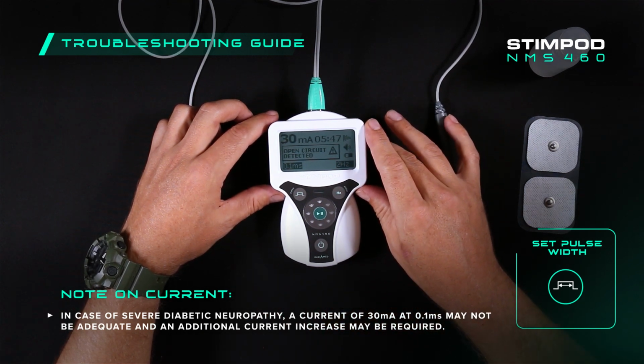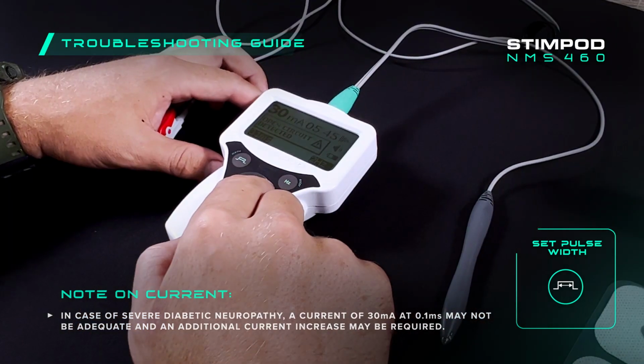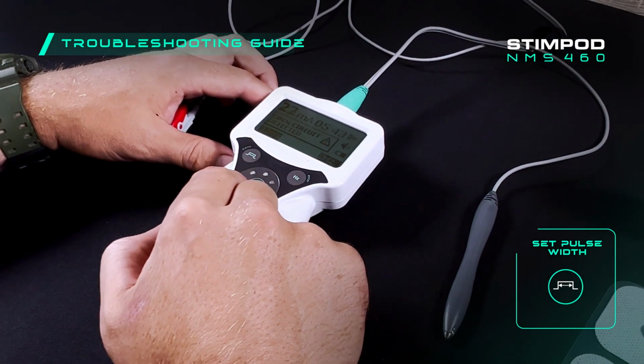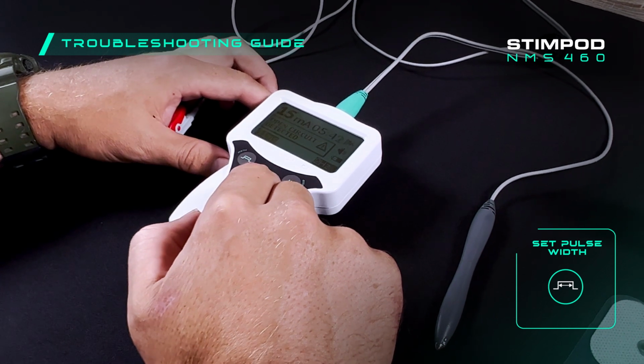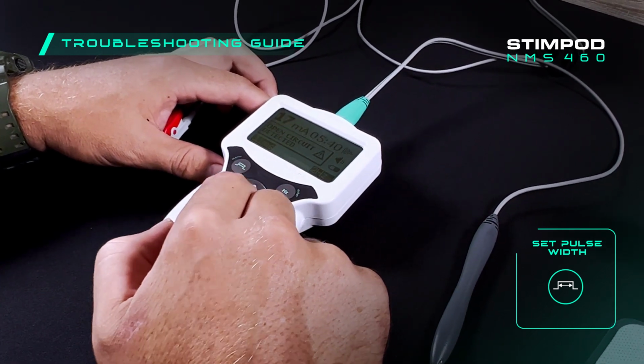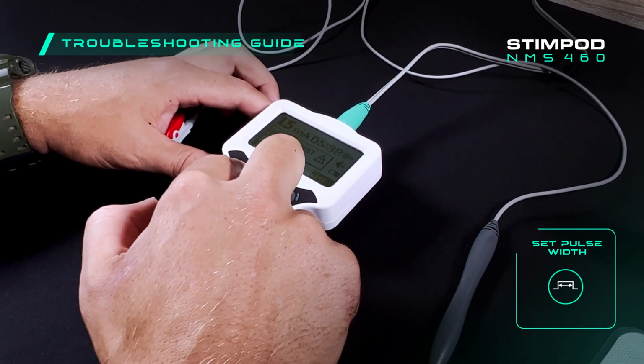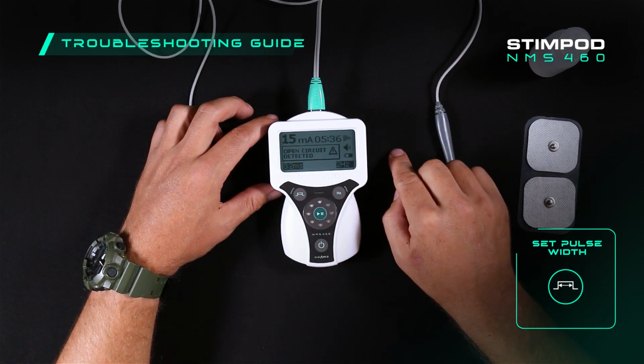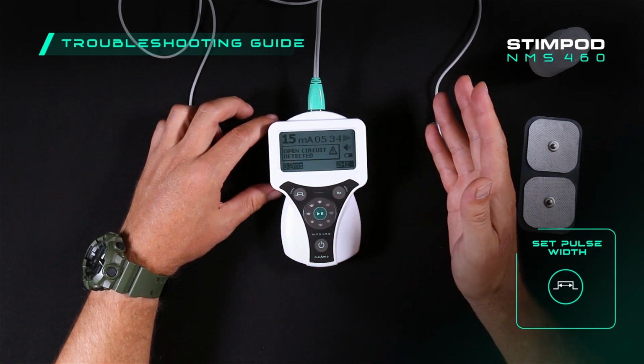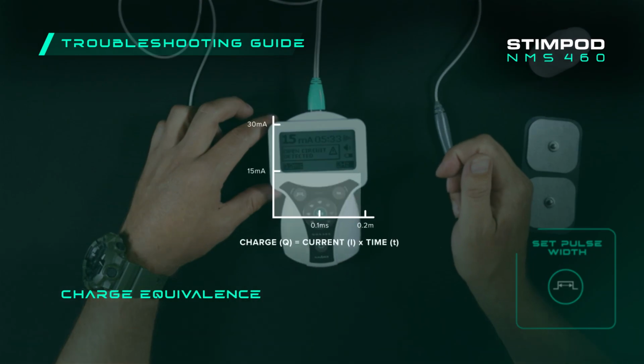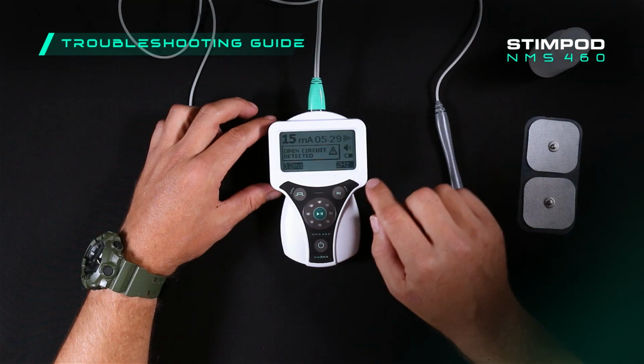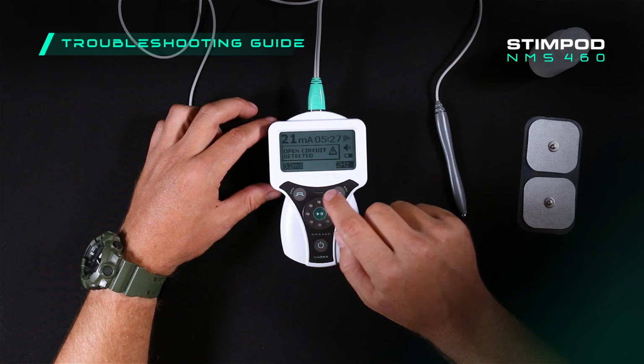This is common in patients with severe diabetic neuropathy in the lower limbs, but may also present in other conditions. If this is the case, you can turn the current down to 15 mA and set the pulse width to 0.2 milliseconds. A setting of 15 mA at 0.2 milliseconds will deliver the same amount of charge as 30 mA at 0.1 milliseconds. You can now increase the current to the desired level.